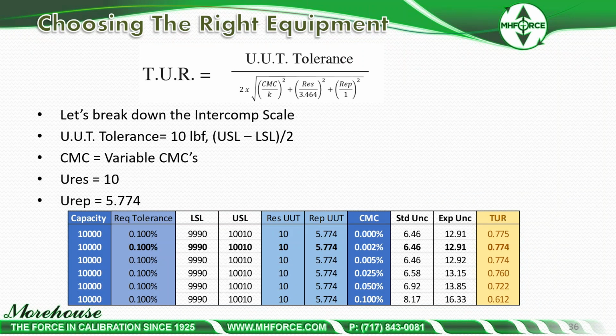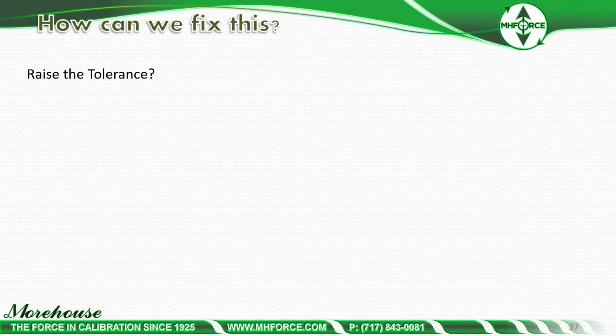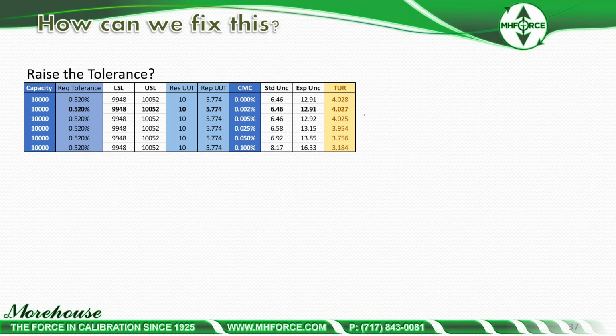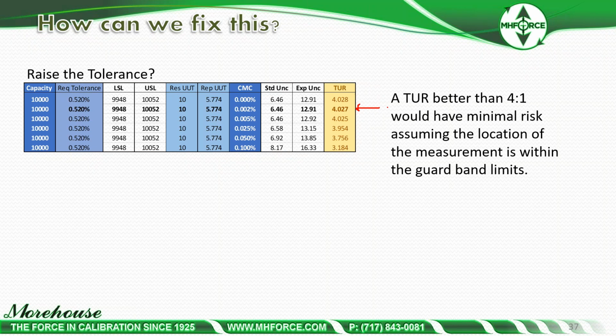But if we break it down, you start looking at resolution, you look at repeatability, you look at TURs, you look at expanded uncertainties, and you can see that the CMC's not really doing much to the TUR until you get to 0.1%. So this is clearly the issue here with anything: it is not the reference standard. The reference standard, as long as 0.05% or better, the TURs, it's the instrument that we're testing. So if we look at how we can fix it, we can raise the tolerance. If somebody wanted a 4-to-1 TUR, we would need to raise the tolerance to 0.52%, and we would have to use dead weight as a primary standard. So this would have minimal risk.